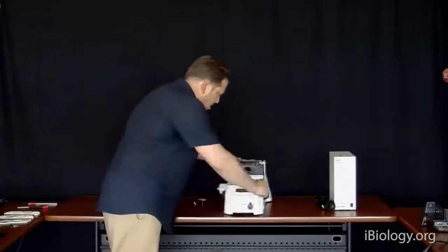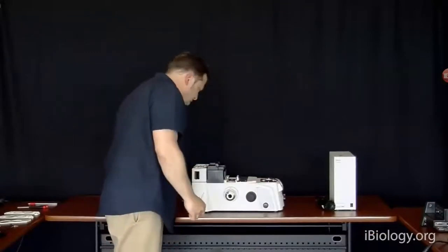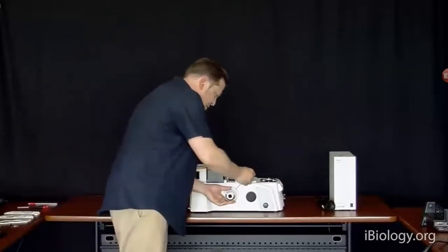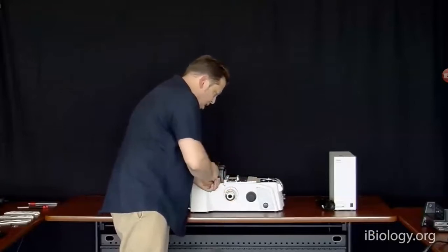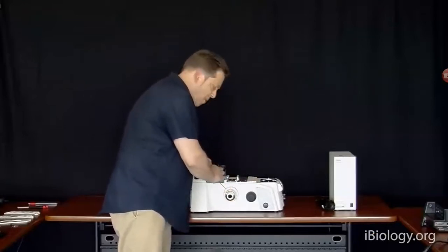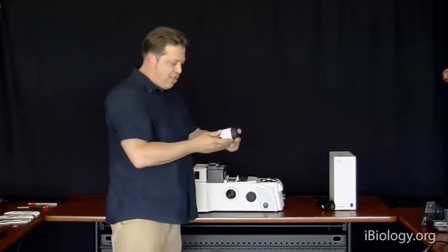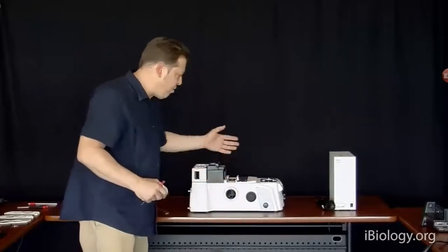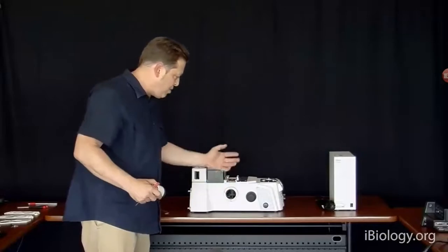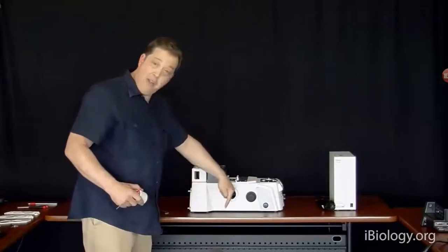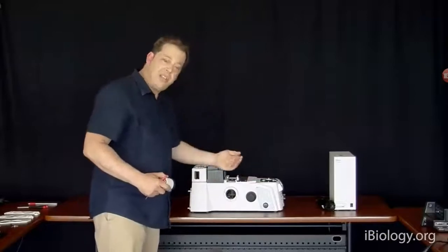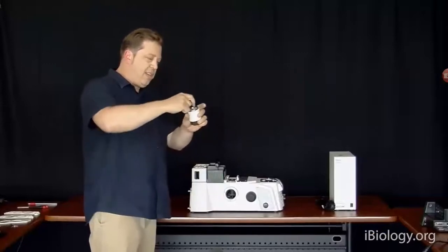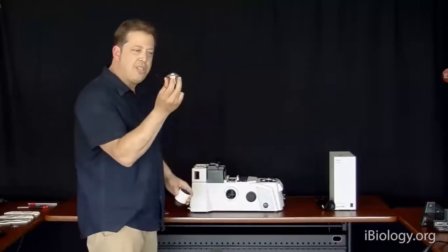Okay, the last component that I'm going to talk about is a relatively simple but very important one, and that is the imaging port on the microscope. Now, everything we do is for efficiency. That's why we use the tube lens method rather than adding a lens to magnify. And we have what's called the side port of the microscope. And in here, you basically just have a turret of prisms that'll port the emission light from the specimen out to cameras on either side or on the bottom of the microscope or up to the eyepieces. And your cameras or detectors would be on this component here called an ISO C-mount.